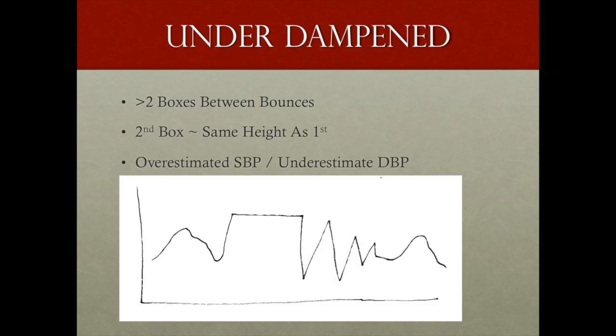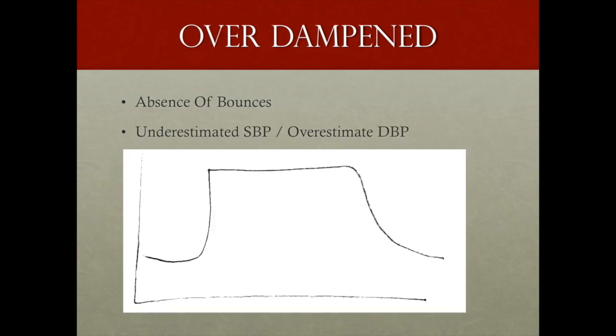When you perform a square wave test and see greater than 2 boxes between bounces, with the height of the second wave close to the same as the first, it takes longer to oscillate down back to baseline. An example of an over-dampened square wave test would be the absence of bounces—you pull the pigtail and release, and it slowly drops down back to its baseline. That would be an over-dampened tracing.